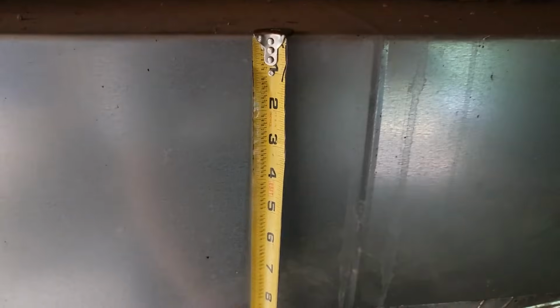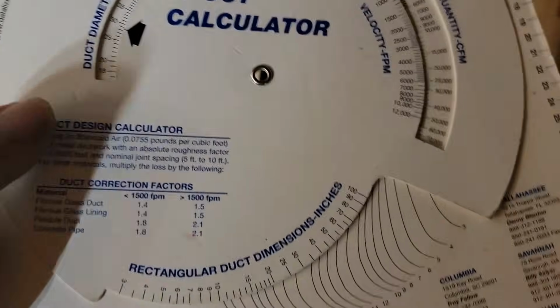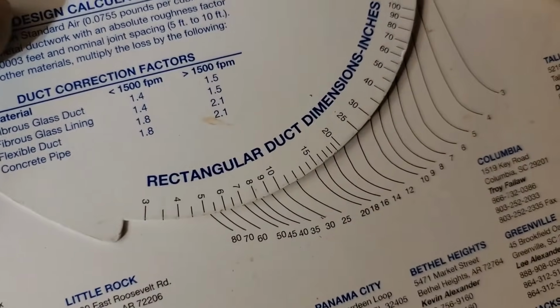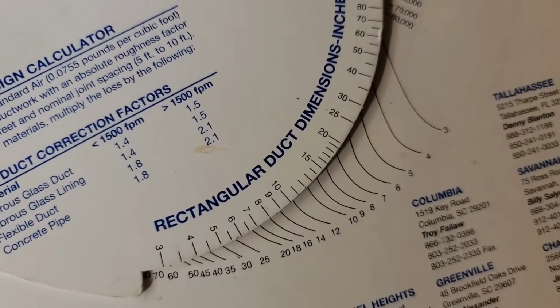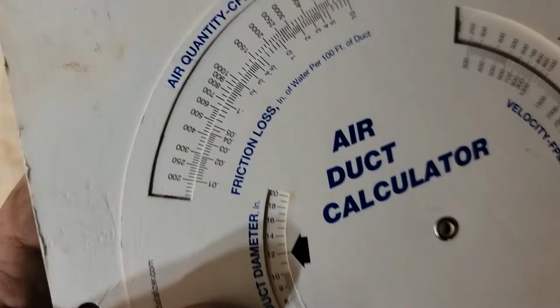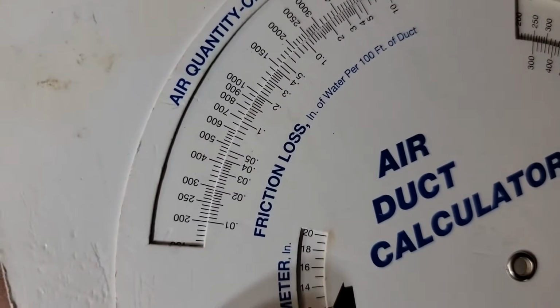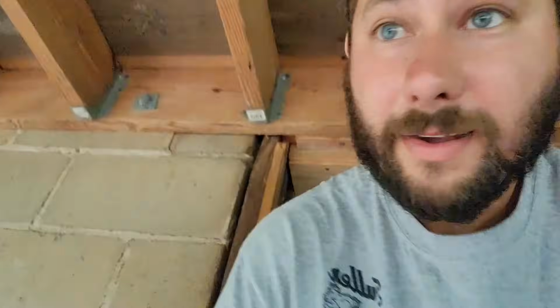See what our other size of duct is. 12 by 10, looks like 12 by 10. It's also insulated on the inside, so you lose a little bit there. So let's go to 12 by 10. Line that up. 12-inch duct, 0.05, does about 480 CFM. So we got 4 vents right here. That'll be perfect. So we take off about 3 ducts with this, and then 3 more supply vents here. So at least it's proportioned pretty good. All right, let's get out of here. I'm gonna go run some service calls, come back, see what we got.